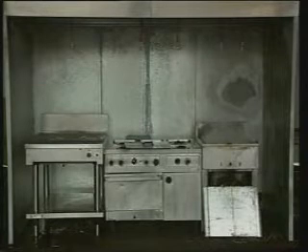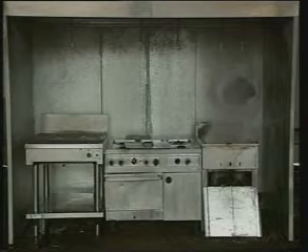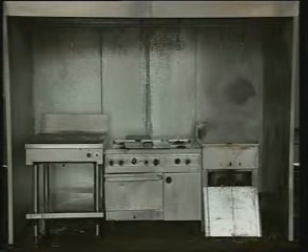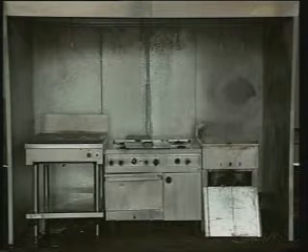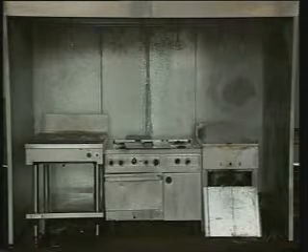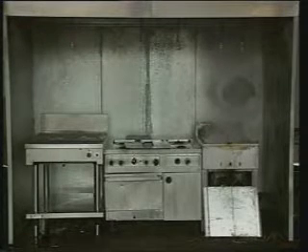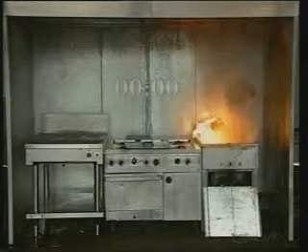combating such fires. For the first fire demonstration, commercially available cooking appliances were positioned beneath an extraction hood. An Ansul R102 system was installed with fixed nozzles protecting appliances, hood, plenum and extraction duct using Ansul X wet chemical agent. The deep fat fryer was filled with vegetable oil and steadily heated to the oil's auto-ignition temperature of 350 degrees Celsius.